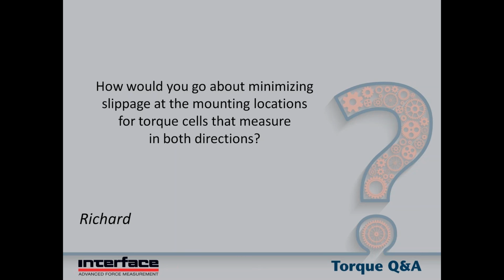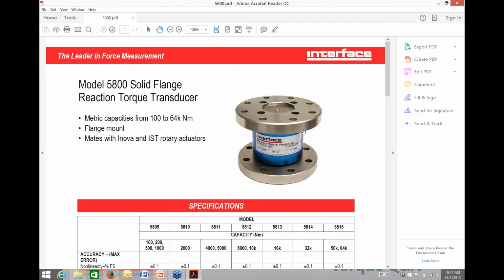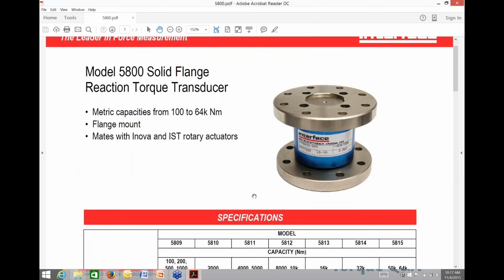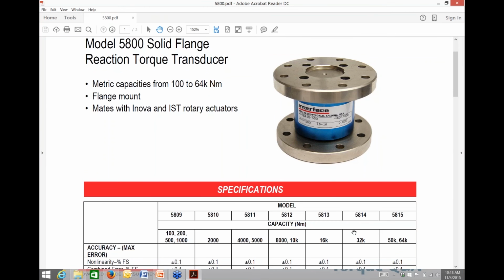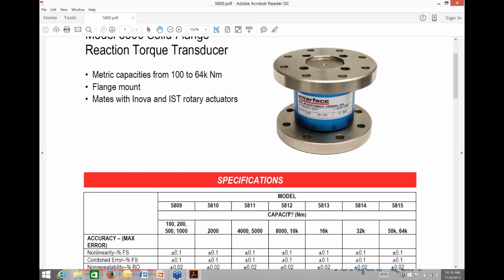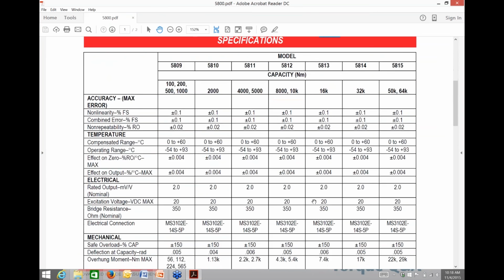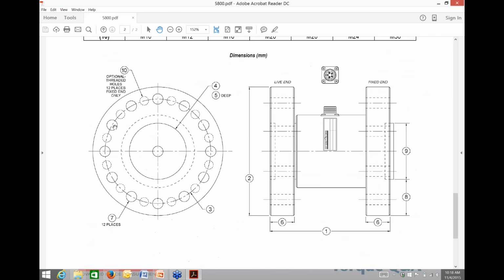And one example actually is a design of a flange sensor that's been around a long time. There are many companies making it at this point, but some of those sensors have, say, a little too much slippage at their higher capacities, and so we can do a sensor that basically has more holes. I can show you an example of something like that here. This is a sensor, basically our 5400 series, which drops in for sort of an industry standard package. But in some cases, like the 50K and the say 100K capacities, the 50K and the 100K capacity are in the same package. So the 100K capacity in that package tends to have that issue. And so this would be an example of that same sensor with an improved mounting configuration, basically with a lot more holes. So you can either have more holes, you can have bigger holes, or you can have them on a bigger bolt circle. And so those are things that can be done to prevent slippage.